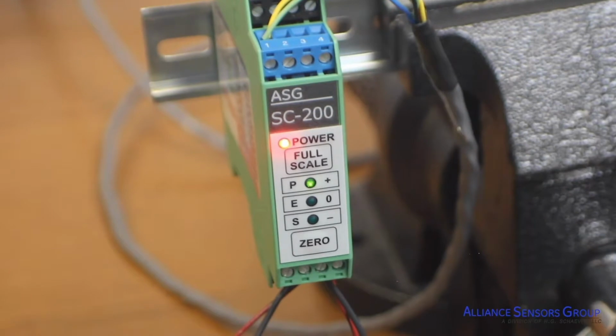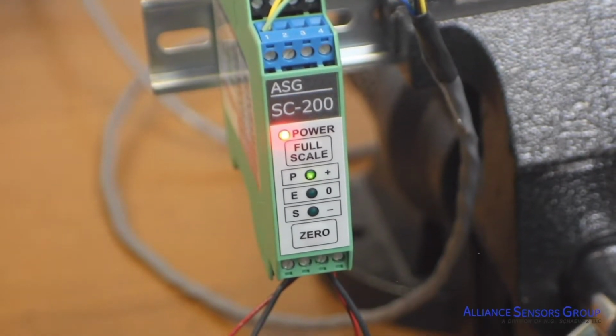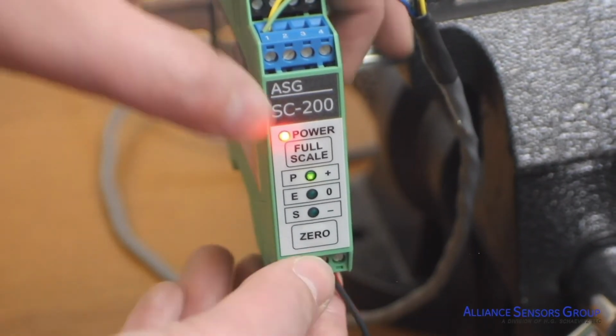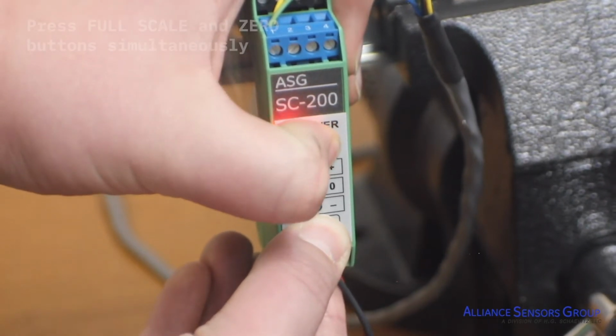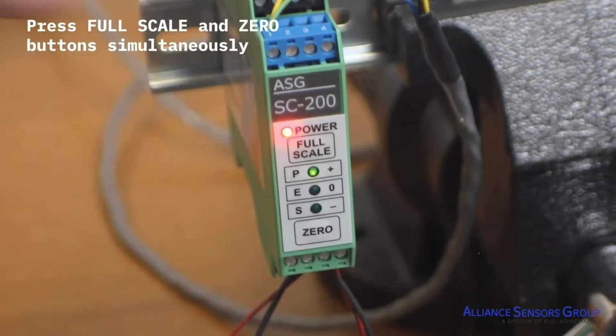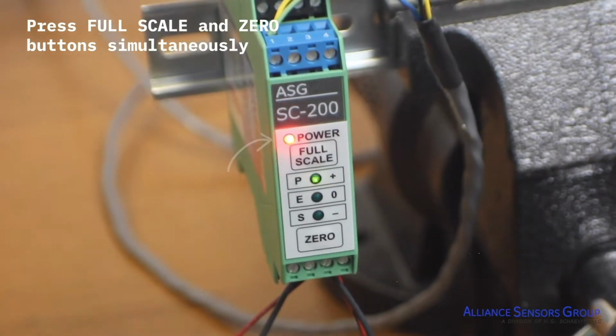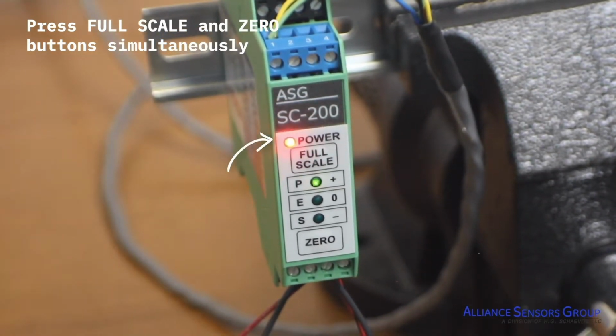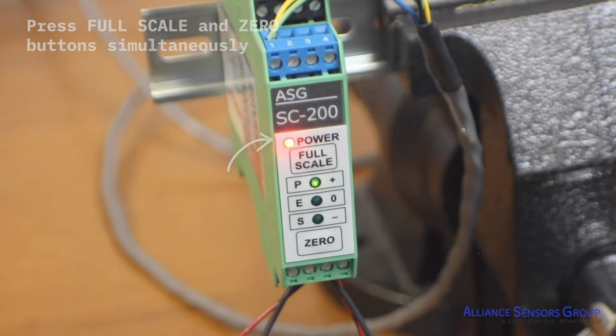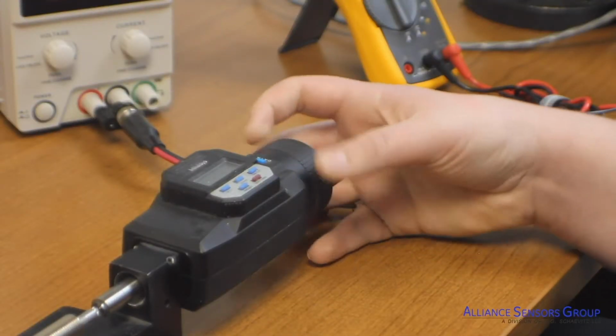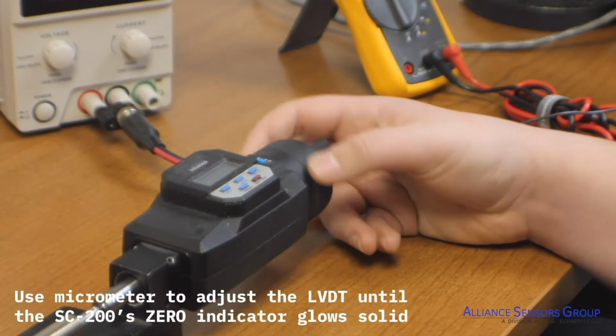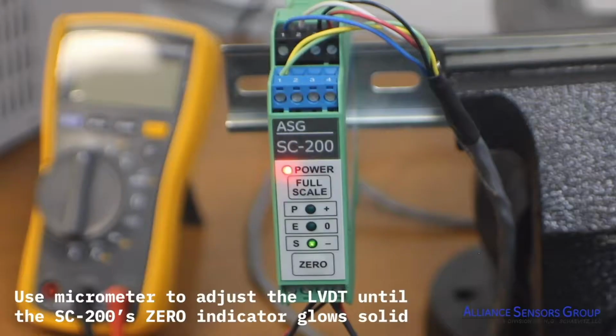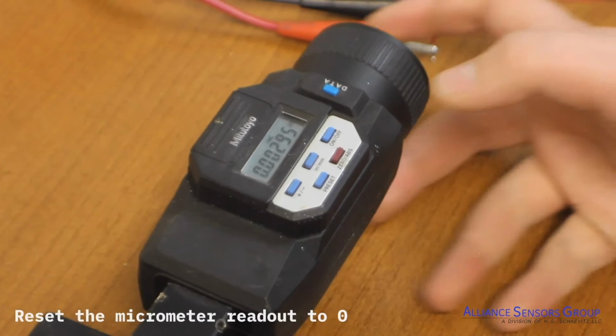With the SC-200 fully warmed up, we are ready to place the SC-200 into calibration mode. This is accomplished by pressing the full scale and 0 buttons simultaneously until the power LED begins to blink, indicating we have successfully entered the calibration mode. Using the micrometer, adjust the LVDT until the SC-200 0 indicator LED glows solid. This is the null point of the LVDT, meaning that the core is at its center stroke. We now reset the digital micrometer readout to 0.